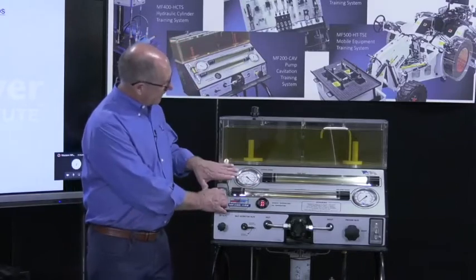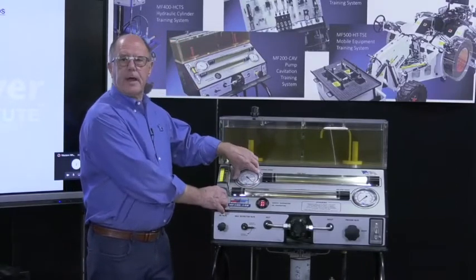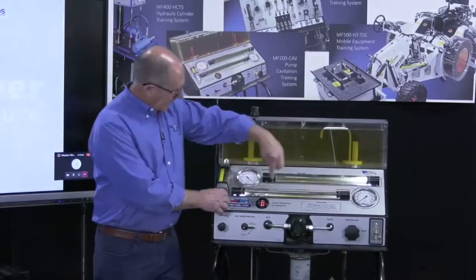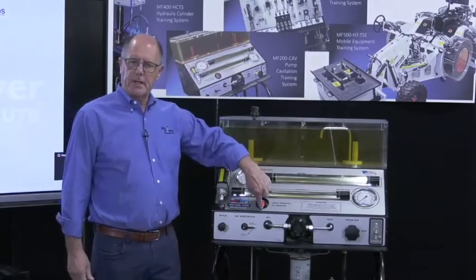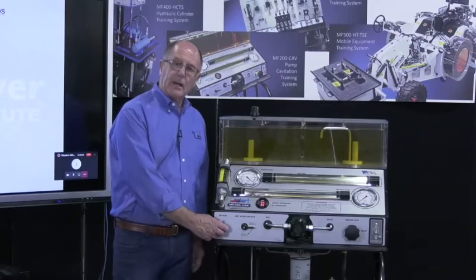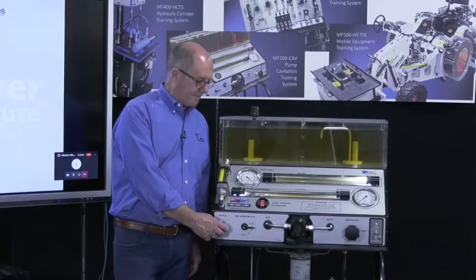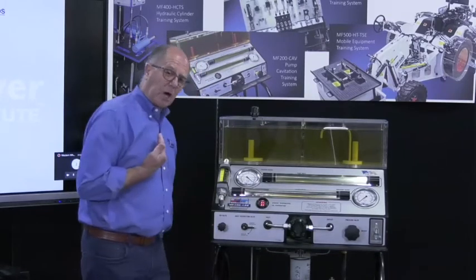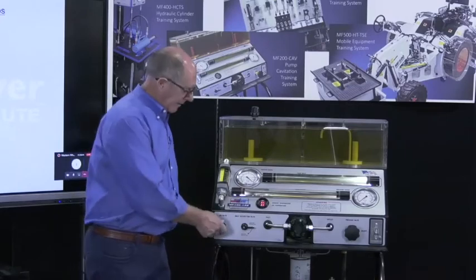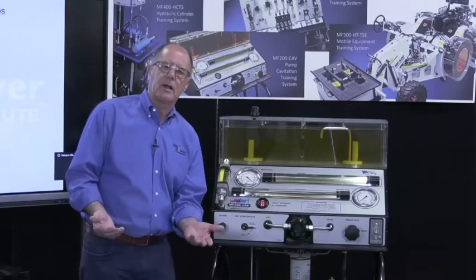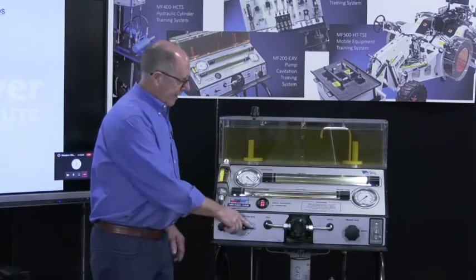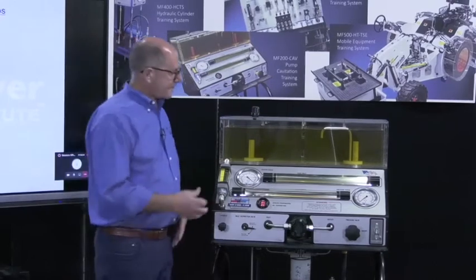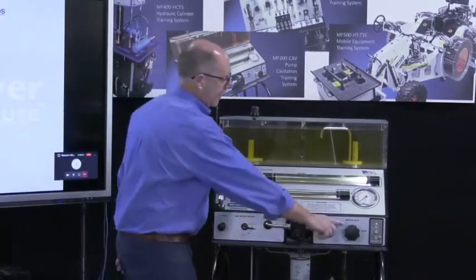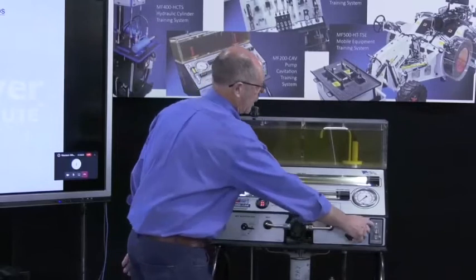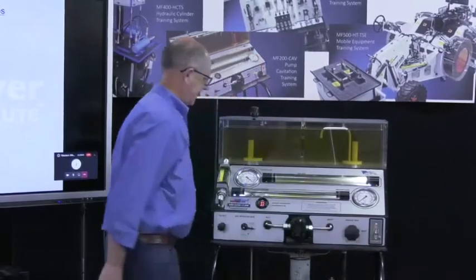We got a flow meter. We got a vacuum gauge, 4-inch vacuum gauge. We got a pressure gauge. We got an ambient and oil temperature gauge. Then we got a valve here that'll allow me to let air go into the intake of the pump. I got a valve here that'll allow me to starve the pump. So that would be, let's say, low oil level starvation. Let's say a plugged screen, wrong viscosity. And then I can make pressure with this guy right here, on/off switch over there.